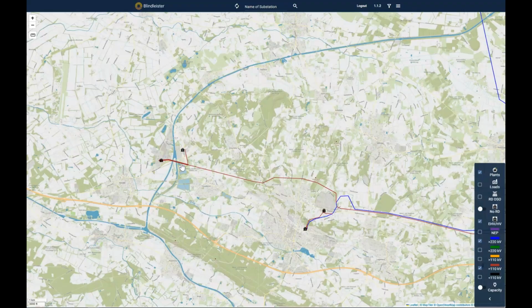So we are a little bit limited, but this also helps to understand limitations, because if we click on this line, we see we have two circuits, 6 cables, and roughly 246 MVA. So that's our maximum capacity that can be transmitted through this power line. But as a rule of thumb, as I said in the video before, we can only assume we are capable of using half of it, because there always needs to be a safety margin in case one circuit is destroyed, we still have another circuit. So we can compute here, we can have around 120, 130 MVA.